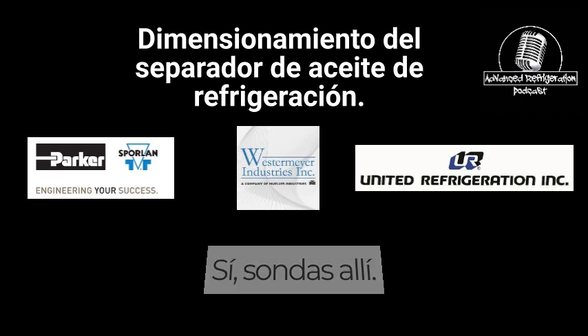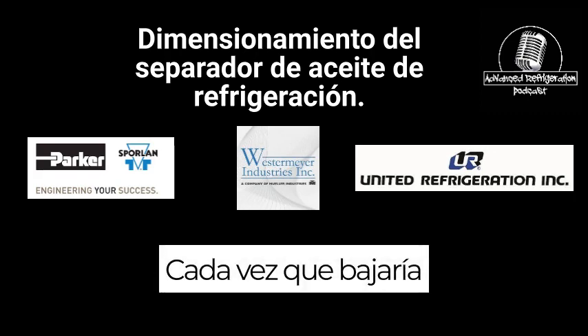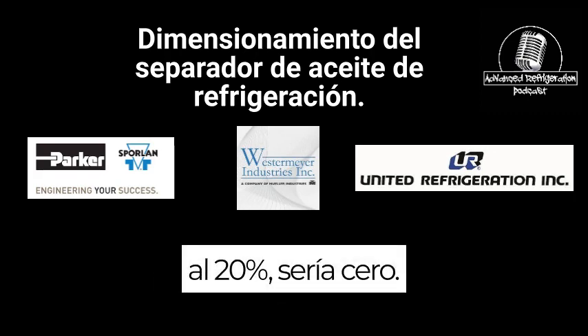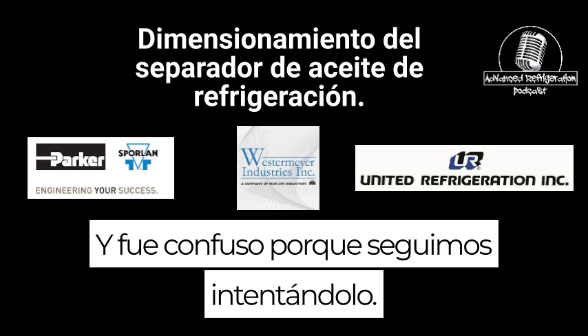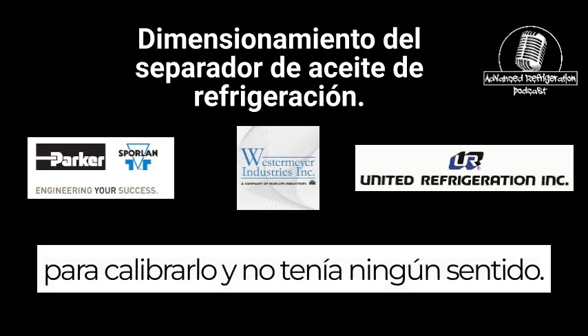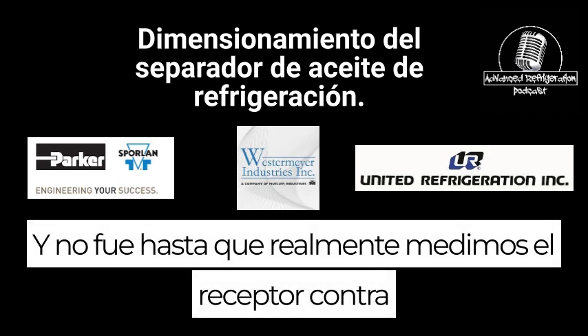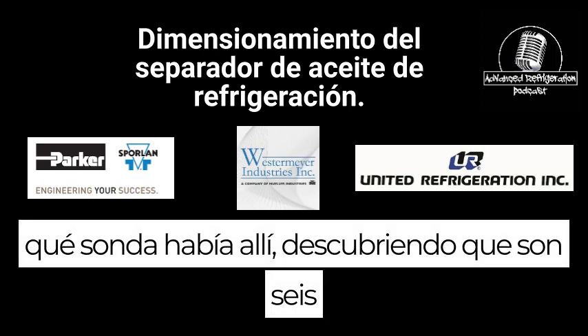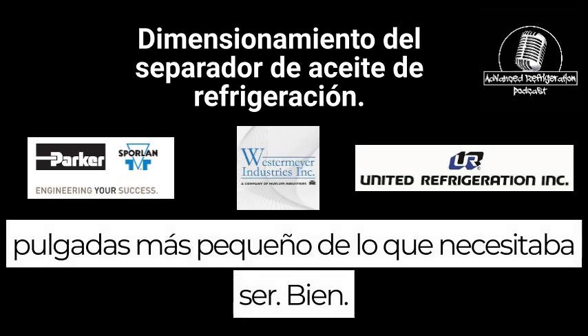So we had a run of Bullseye stores where basically they had 60-inch receivers, but they had 54-inch probes in there. Every single time it would get down to 20%, it would read 0, and it was just confusing because it was calibrated and it didn't make any sense. It wasn't until we actually measured the receiver versus what probe was in there, finding out that it's 6 inches smaller than what it needed to be.